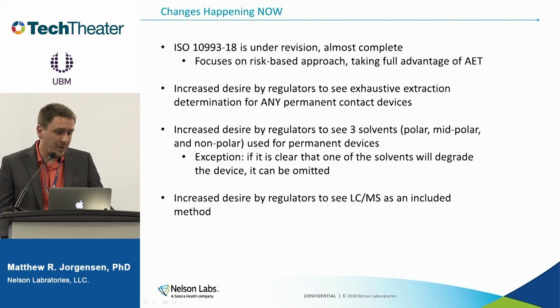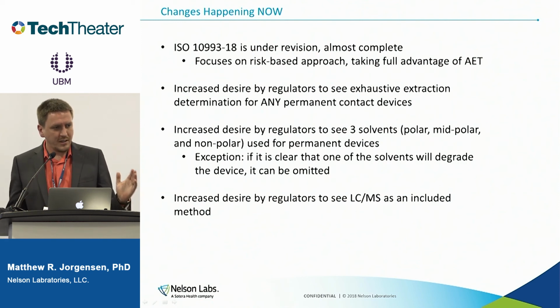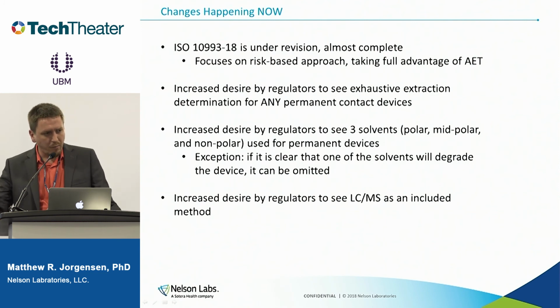We also see an increased desire by regulators to use 3 solvents. So in the past, we felt pretty good about spanning this range from polar, very polar with water, to very non-polar with hexane, and saying, okay, well, anything will land in between. Now we're seeing a lot more requests to include the mid-polar, even if you include a non-polar solvent. So this is something that's coming up that you should be aware of. Of course, the exception there is that if you damage or degrade the device, clearly that solvent isn't going to be relevant from a toxicological perspective. So if it degrades the device, that can be omitted. And then we also see an increased desire by regulators to see LCMS included as one of the analytical methods for the device. They really want to make sure that those non-volatiles are being hit.